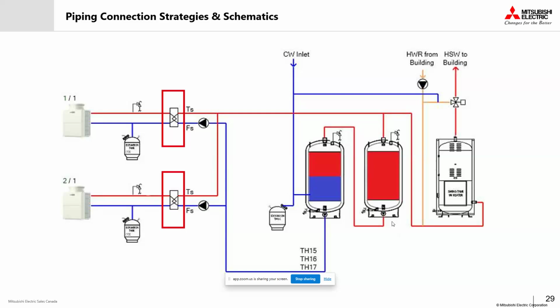Another thing that you'll notice here is if you take a look at our cold water inlet, we're bringing domestic cold water directly from the city and heating it from a single pass through these highlighted heat exchangers. So as Rizwan mentioned, and as I've mentioned a couple of times, we're taking quite cold water from the city. We're managing that at a very high delta T, high lift, and we're heating that directly to our storage temperature that's required for our building.